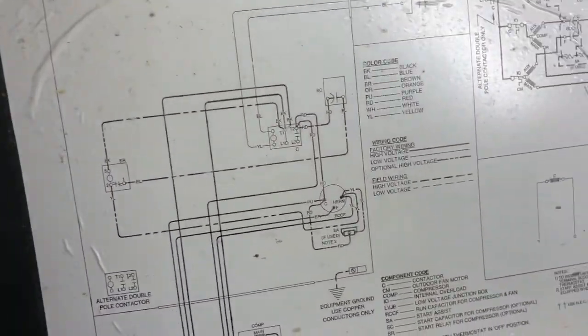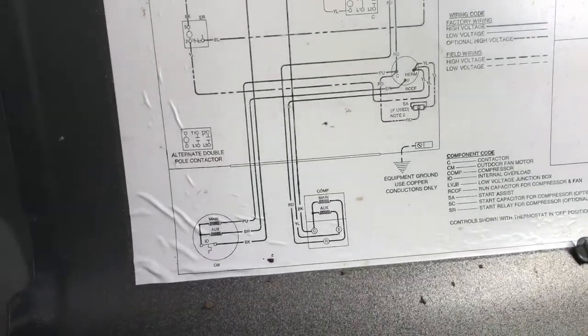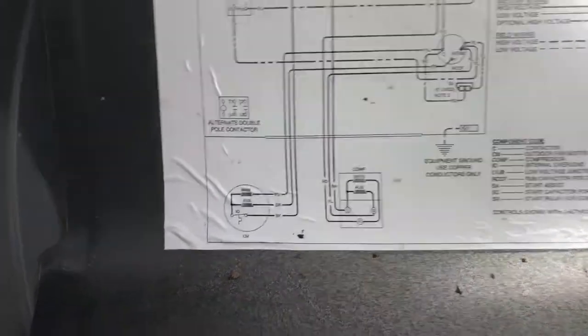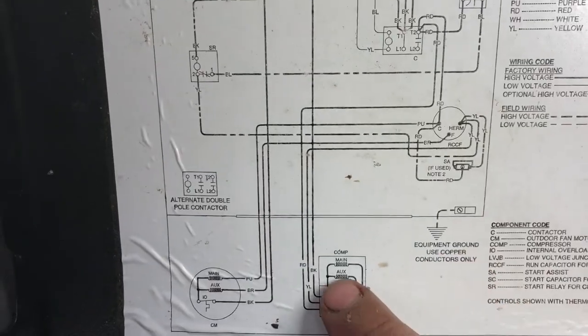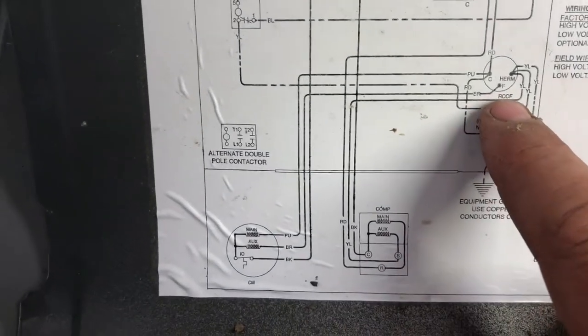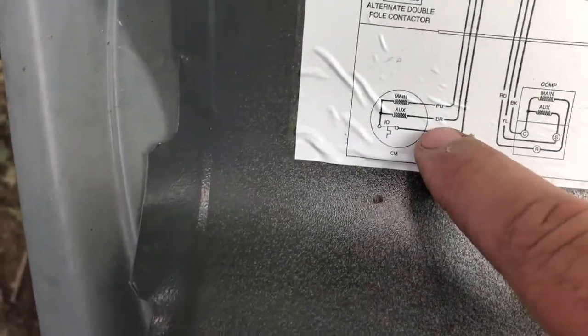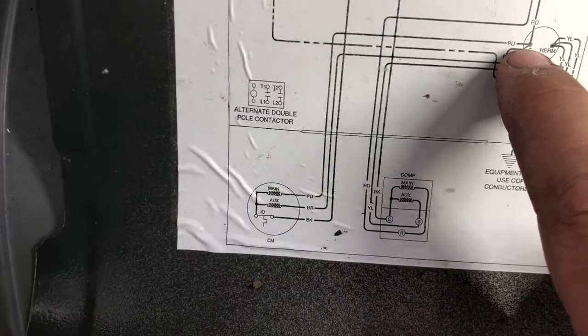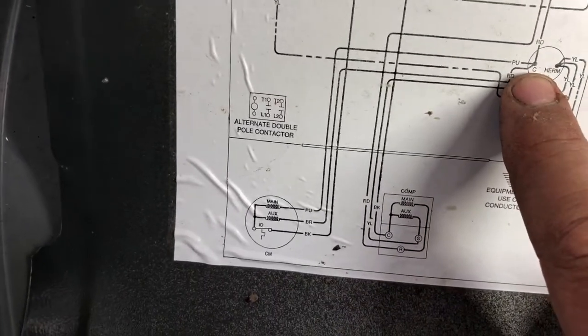This could help you out if you've got something you can steal a capacitor out of, like a window air conditioner, to get it going while you wait for the part. You can see here - HERM, the yellow part, goes down to the compressor motor. Then you'll see F, which is the brown wire going to the fan. Then you'll see PU for purple, and that hooks with red - that's the C for common.